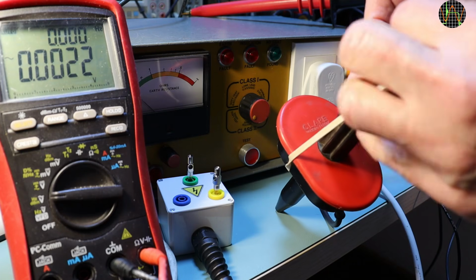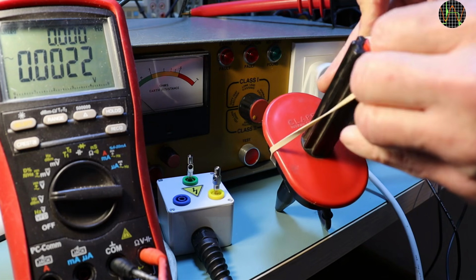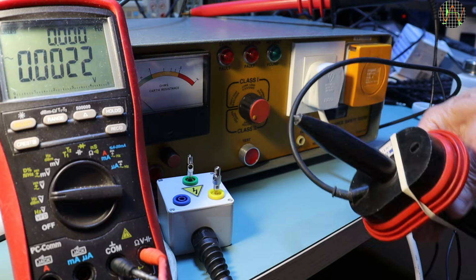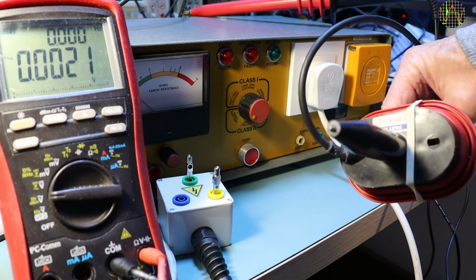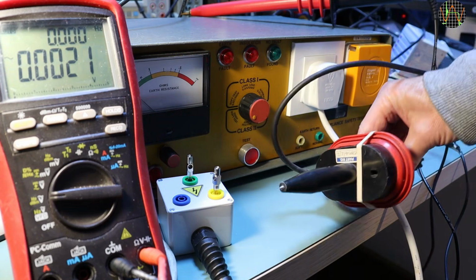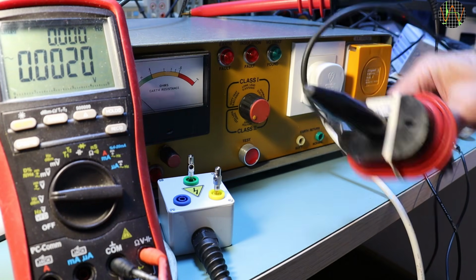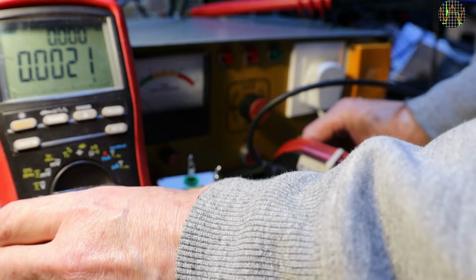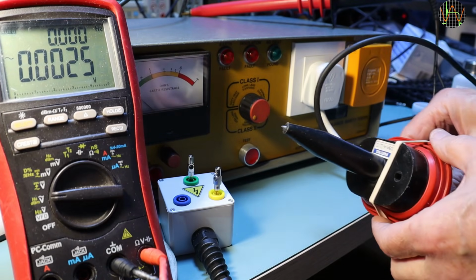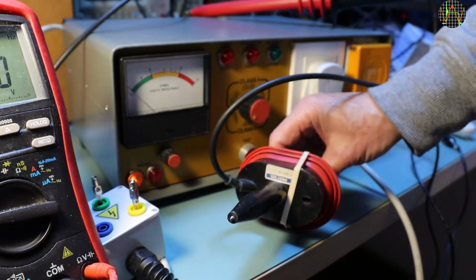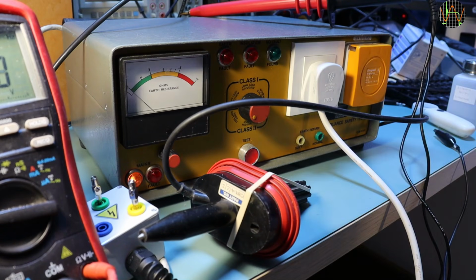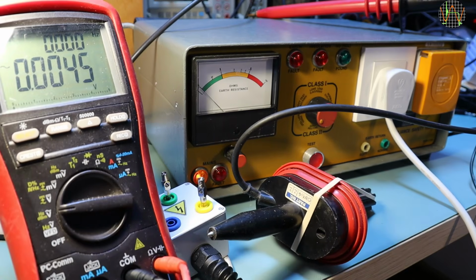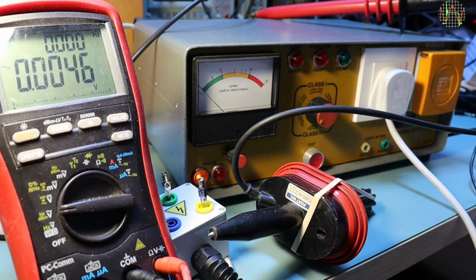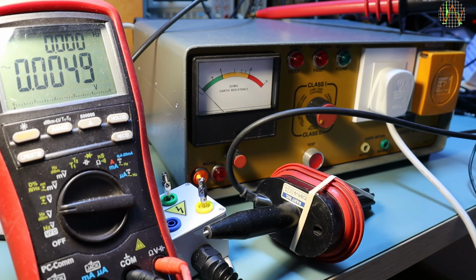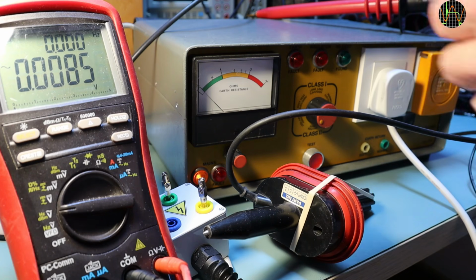For class 2 there is no earth, so the high voltage is applied between the shorted live and neutral terminals and the separate high voltage probe. You are supposed to use that probe to poke the device under test. For example, you would touch the metal part of a USB connector in a USB charger. Sounds like fun? I don't know. Well, let's first measure what we get in class 2 tests. I would rather use only one hand with my 40 kV rated probe, so I make my life easier by using a rubber band to force the tester probe tip to be exposed all the time.